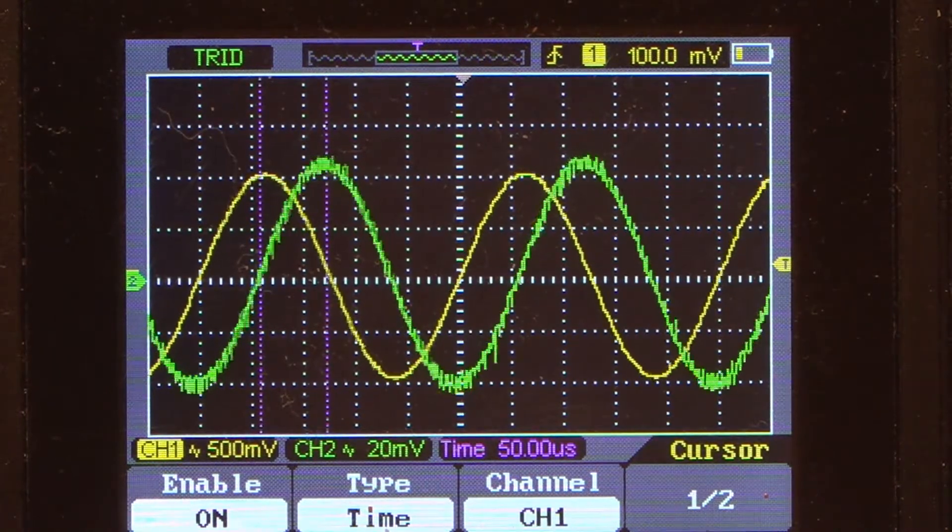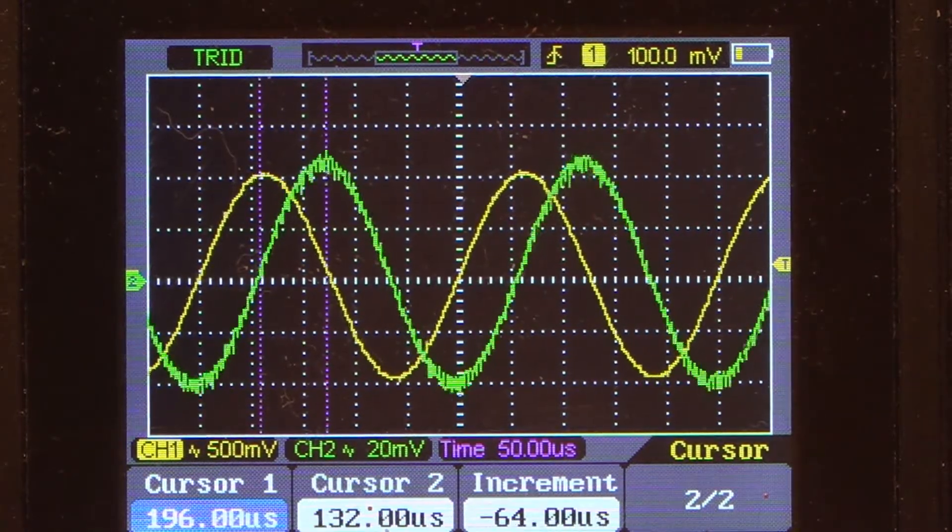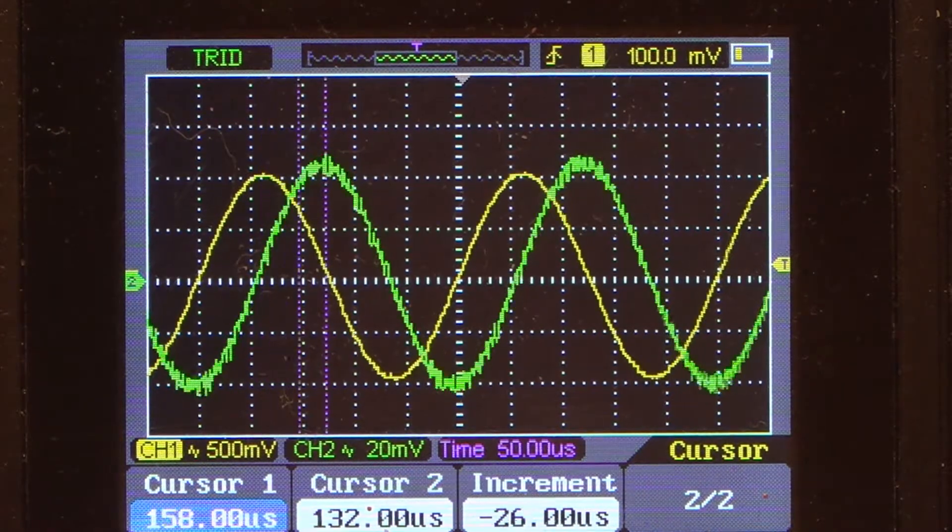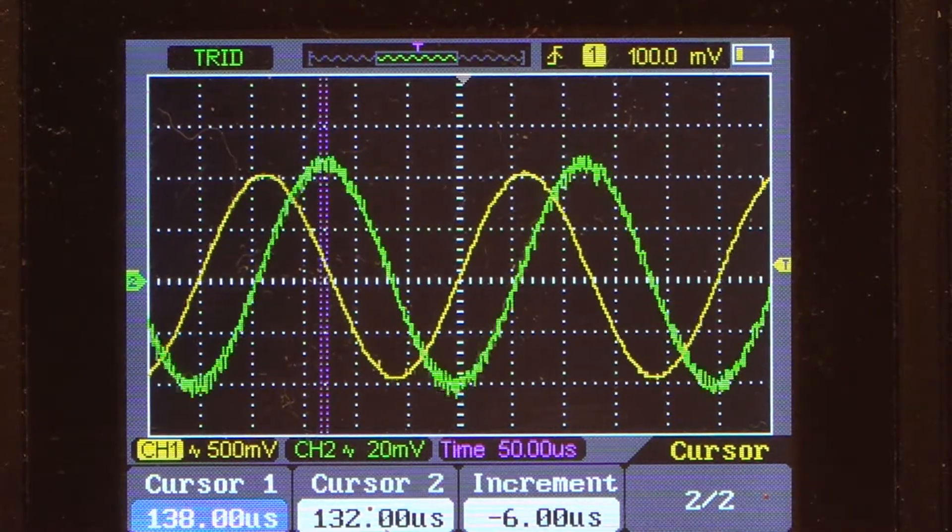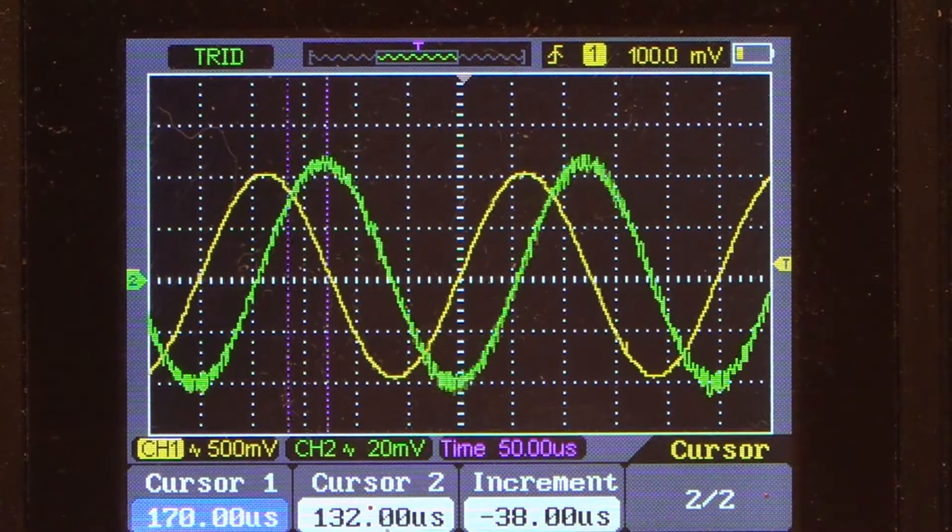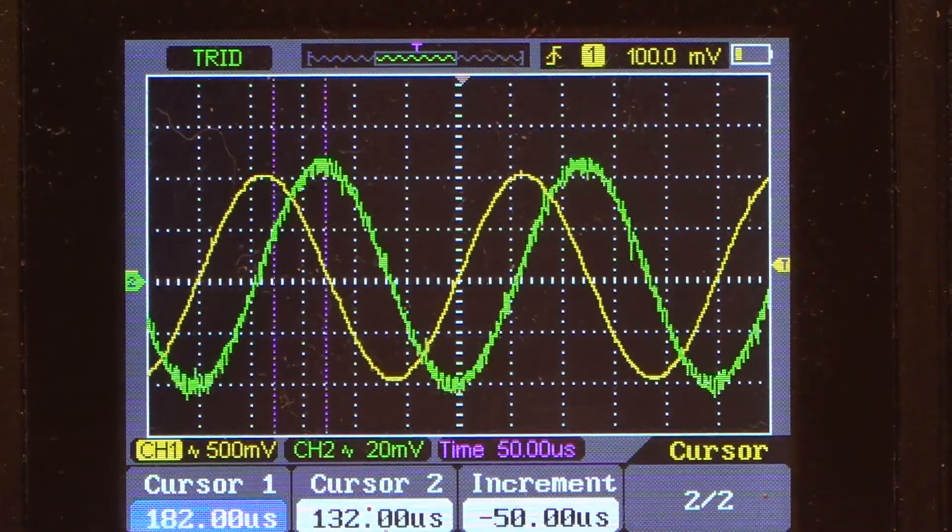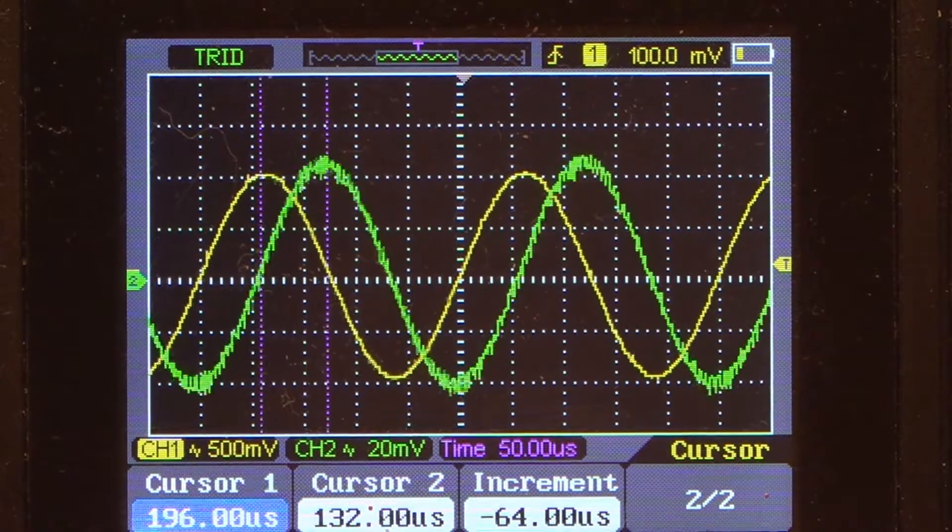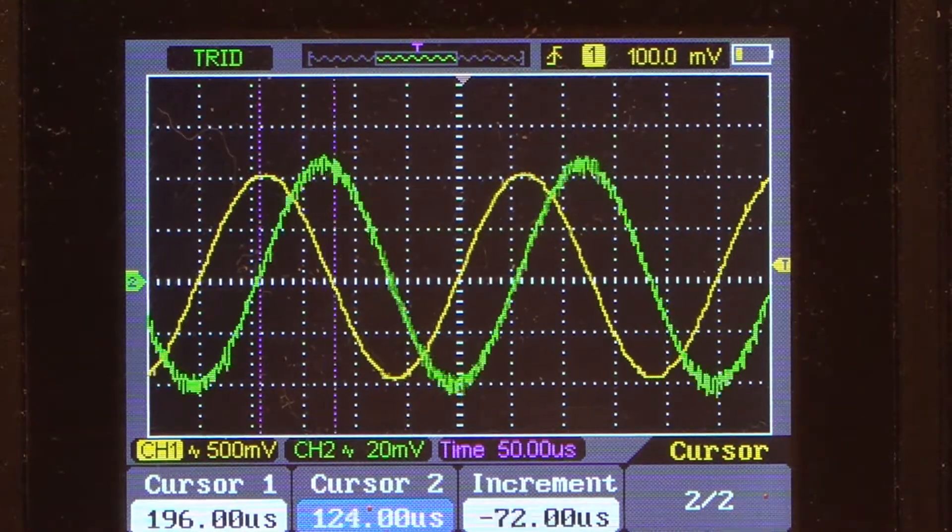So now we can switch it over to time and under time you can see that we get two purple vertical lines. If I go to menu, second page of the menu now, cursor 1 moves the left line to the left and right. And if I slide over to cursor 2 it slides the right line left to right.